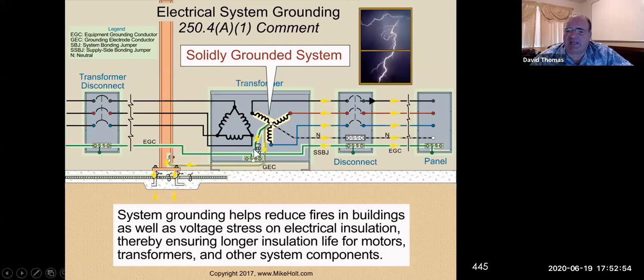We can use this as a pathway to get rid of all these unwanted electrons. For example, if we tie it into the system and, in this case, lightning were to hit our wires or get into the building, it's going to dissipate through the main bonding jumper right in here, and then it will eventually go to Earth through the system, and so that's how that works. Okay.